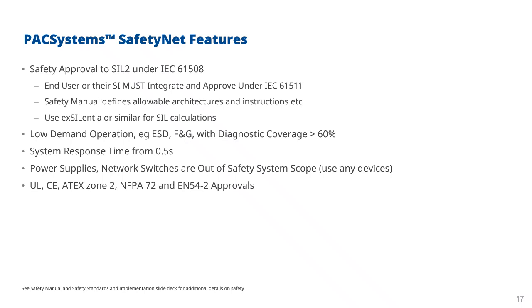about 5 seconds. So, for example, with a flame detector, that would prevent a spurious reading from, say, a reflection of sunlight coming from, say, when someone opened the window or parked a car in the car park and there was a flash of sunlight which went into the receptor. So typically system response times don't need to be that quick. Equally, they don't have to be that slow either. You don't want to wait minutes. And again, this is where your functional safety assessment will define the effective required response time.